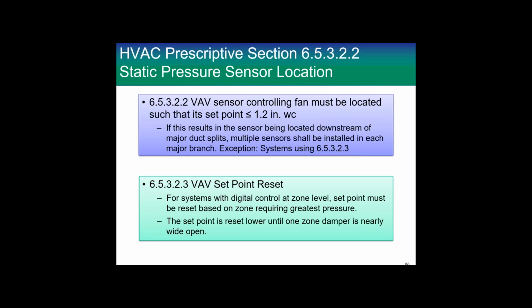Now, you always have to go back to this: the VAV sensor controlling the fan must be located. Because what we're talking about resetting, where the damper is not fully open, you can keep speeding the fan up. What we really mean is you go back to that sensor and you raise the allowed static pressure so the fan would speed up to meet that new static pressure. But you never control the fan from the VAV damper. That would be terrible. It would be way complicated. It wouldn't work properly. You control the set point on that sensor from your VAV dampers, and then that set point controls your fan. And that way the fan's not going to run all over the place chasing those dampers.